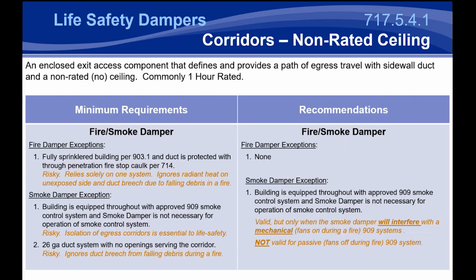And for the most part, you're going to have a fire smoke damper that's protecting that corridor. There's going to be a smoke requirement, and it'll be a separate requirement to remove that smoke damper compared to that fire damper. So we typically recommend fire smoke dampers for these applications. Now, you can remove the fire damper portion if it's a fully sprinklered building and the duct is protected with fire stop caulk per section 714. We think that's a bit risky as there is the potential for some degradation through that system. And as far as I know, per section 714, the fire stop caulk doesn't necessarily need to be certified through a hose stream test that a fire damper would.